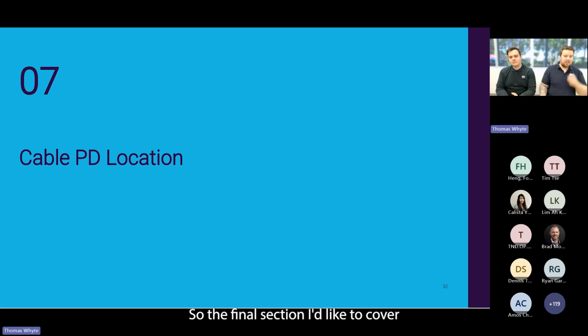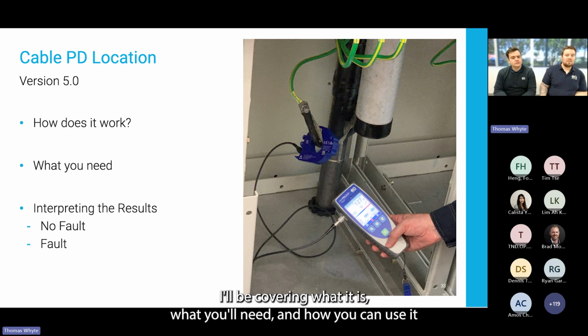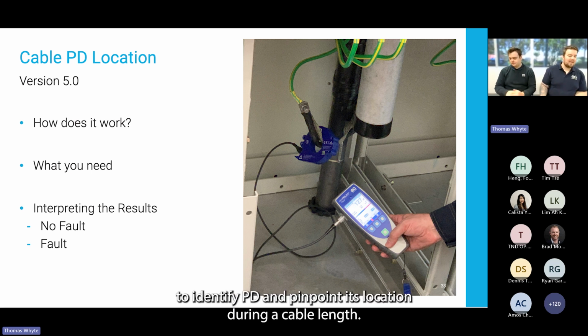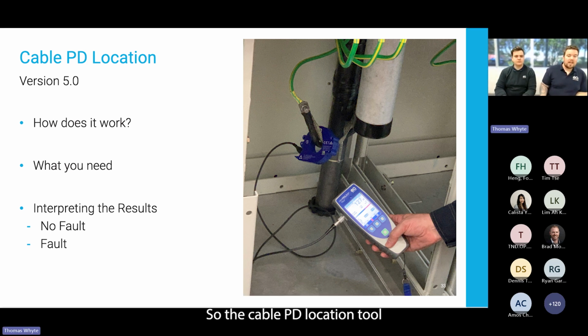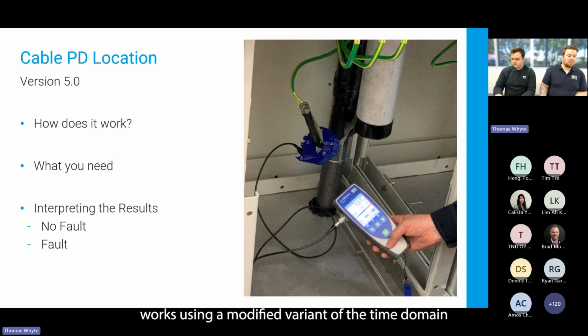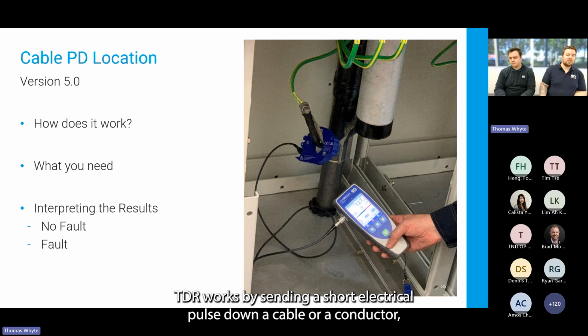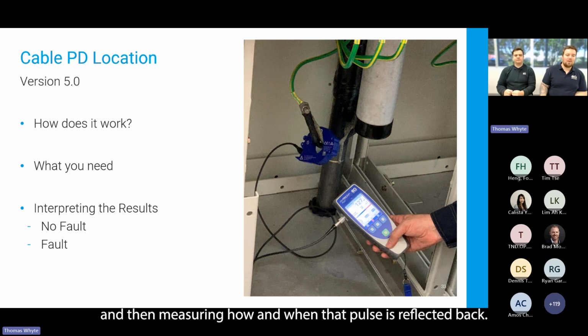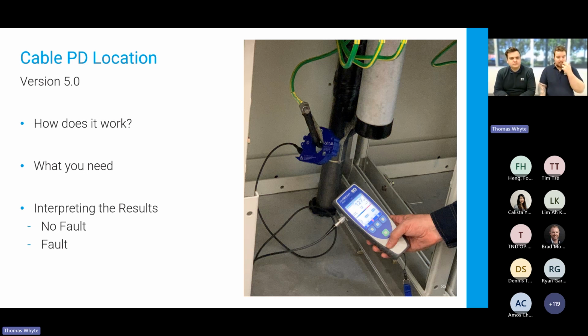So the final section I'd like to cover is the cable PD location tool. I'll be covering what it is, what you'll need, and how you can use it to identify PD and pinpoint its location during a cable length. The cable PD location tool works using a modified variant of the time domain reflectometry, or TDR for short. TDR works by sending a short electrical pulse down a cable or a conductor and then measuring how and when that pulse is reflected back.